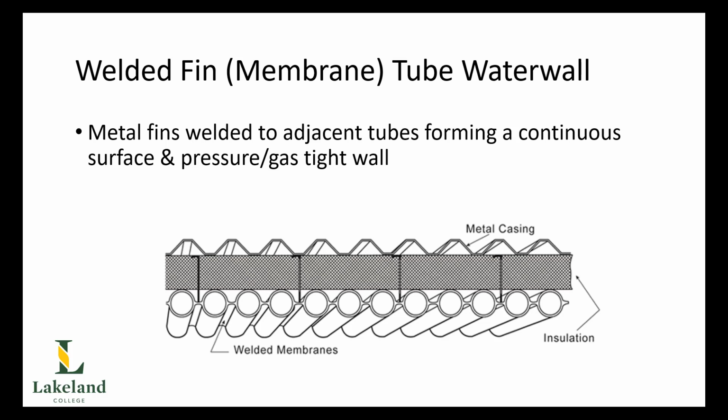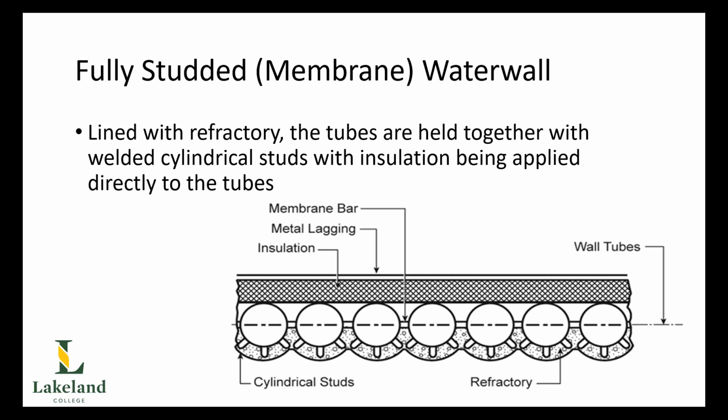You can also see how the water wall is attached to that outer metal casing via these pin studs that hold it all together. And these will form a complete continuous surface throughout the furnace, completely encompassing it, ensuring it's gas tight and its ability to become pressurized without leaking to atmosphere, or with the atmosphere leaking in, depending upon the draft. The next one is our fully studded water wall.